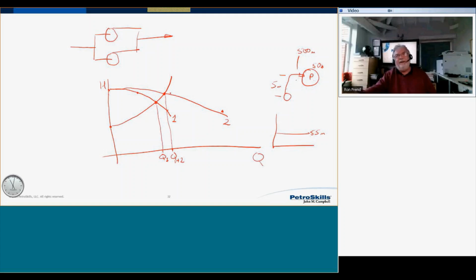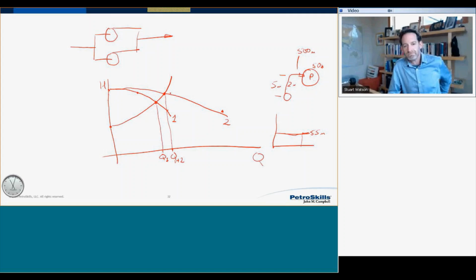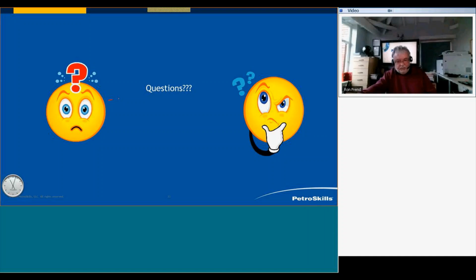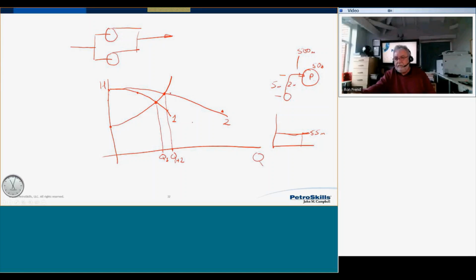How much friction losses do you think you're going to get in there? It's not going to be a lot. Maybe a couple of meters. You add that to the particular design flow, and what you've got is virtually a straight line. Oh, I've gone down a bit. So if you had a system curve which is static dominant, what you end up with is a straight line here, and you would get approximately double the flow. But the more friction you have, the less likely you'll get double the flow.